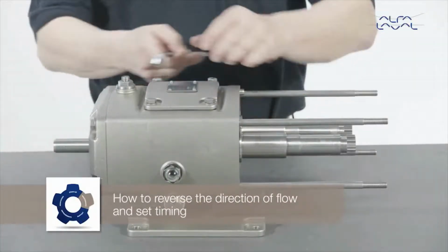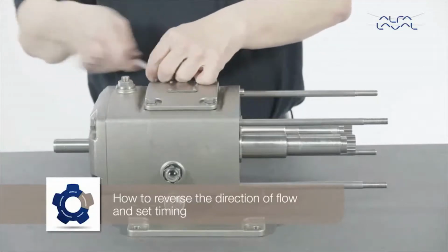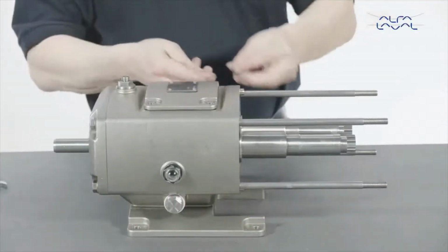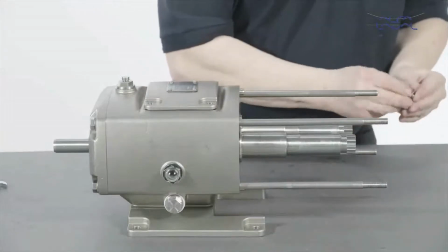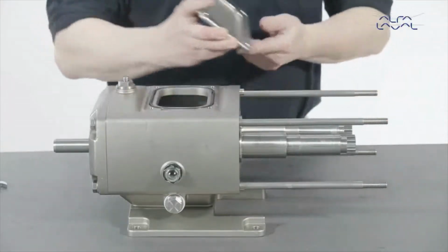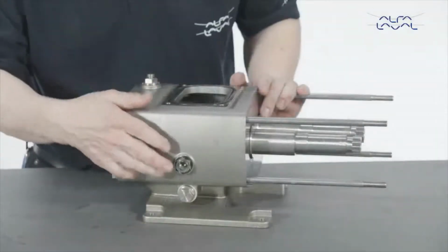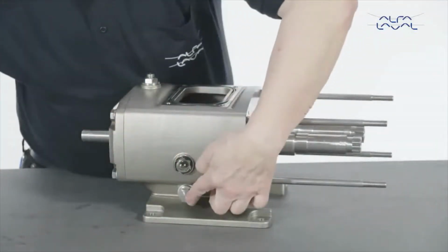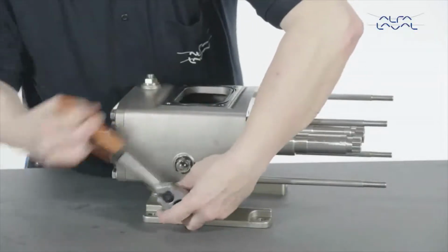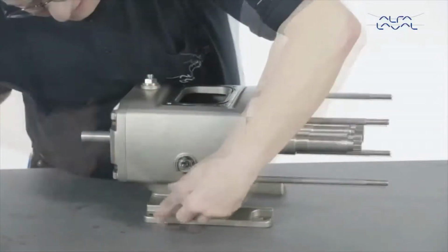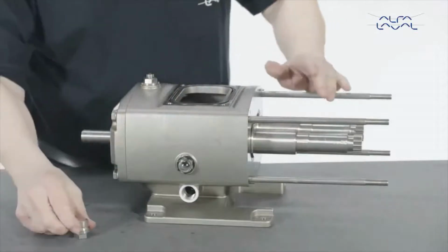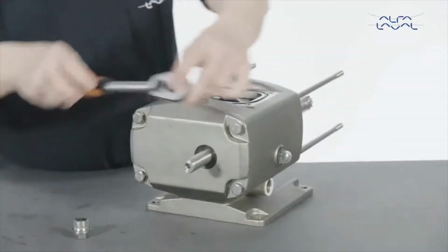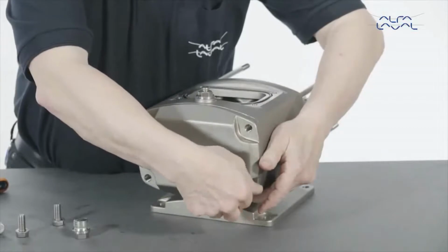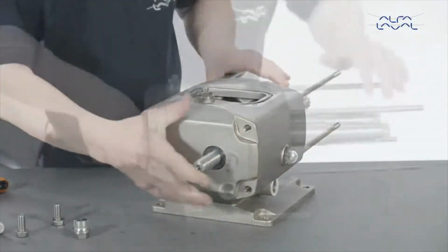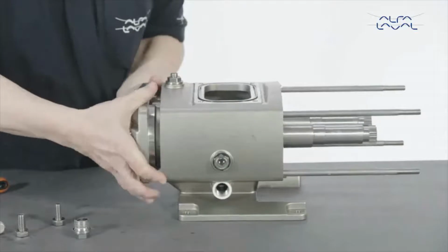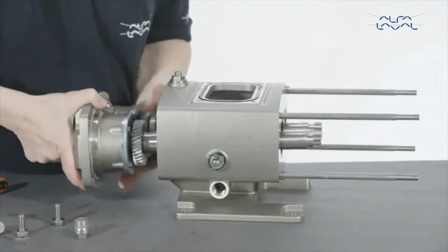How to reverse the direction of flow and set timing. First, remove the gearbox top cover. Ensure that there is no oil in the gearbox. If necessary, remove the drain plug and drain. Now remove the bolts and washers from the gearbox end cover. Then remove the end cover, including the shafts, and fix it in a vise.